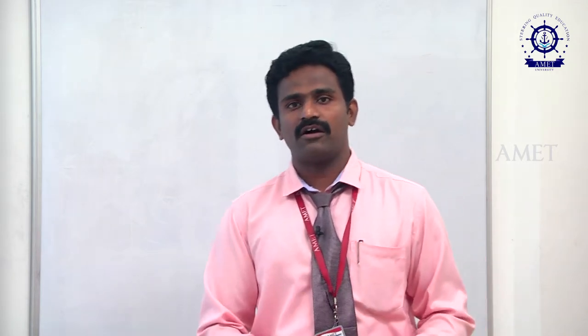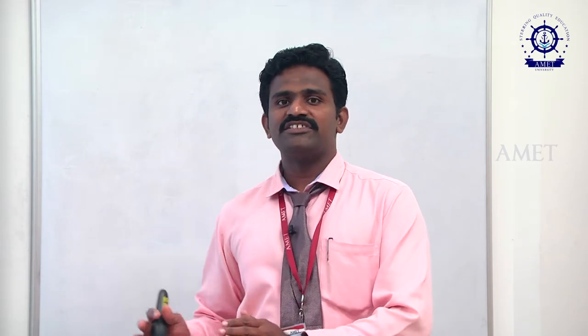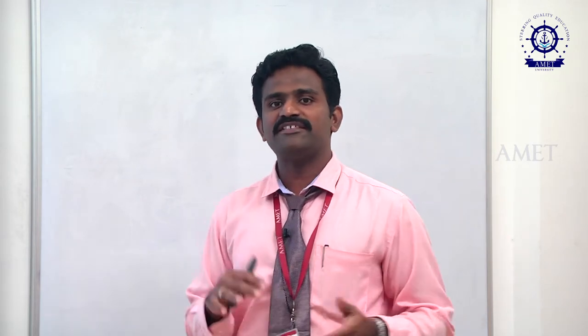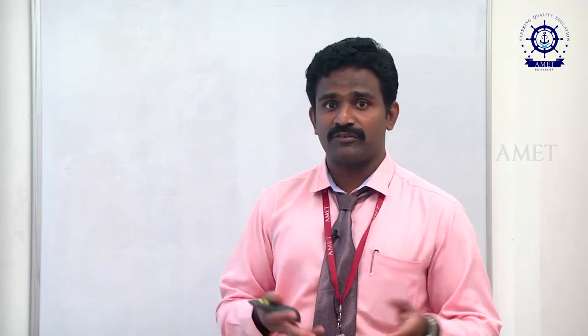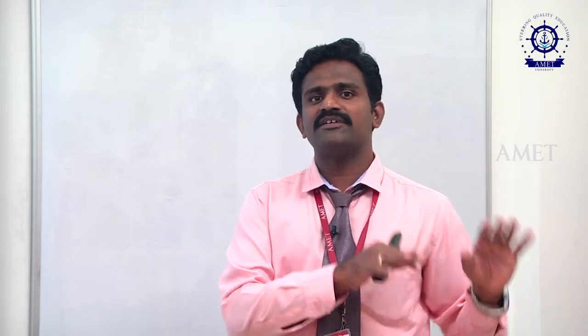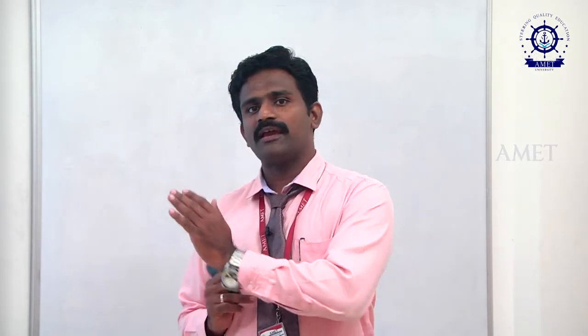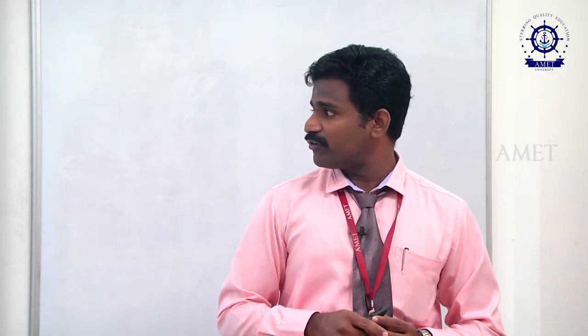Only under that condition will the emergency generator turn on. At all other times, it remains in a standstill condition. It is located outside the main and auxiliary machinery space. This is because we want the emergency generator to be in a very secure location — separate from the main switchboard — so that any power loss, fire accident, or unforeseen situation will not disturb it. It is located outside the main and auxiliary machinery space and not forward of the collision bulkhead.